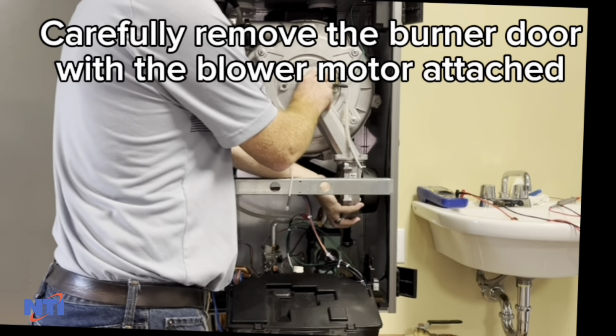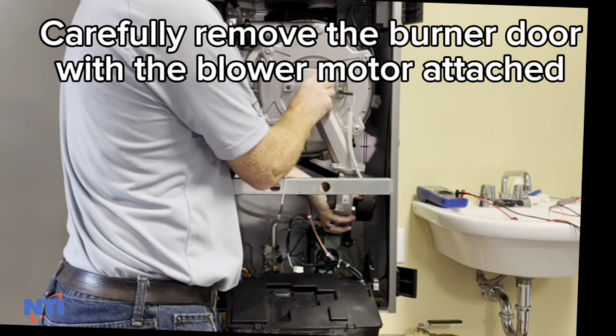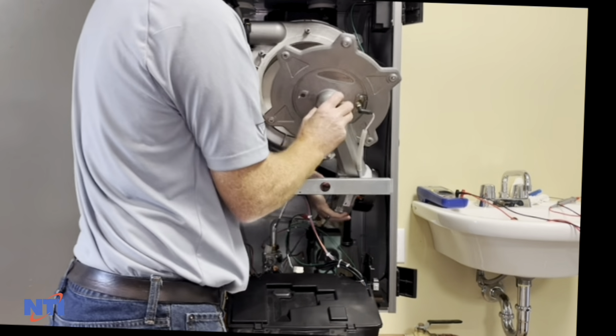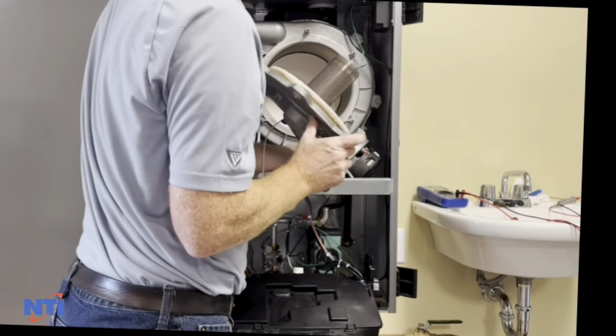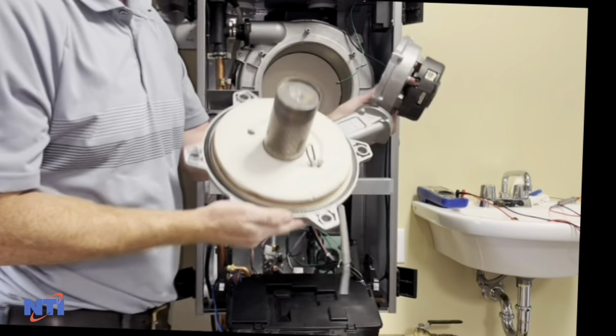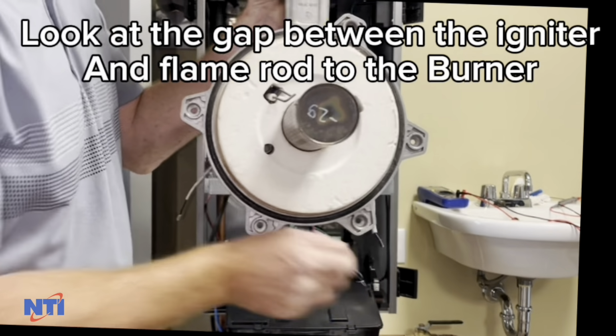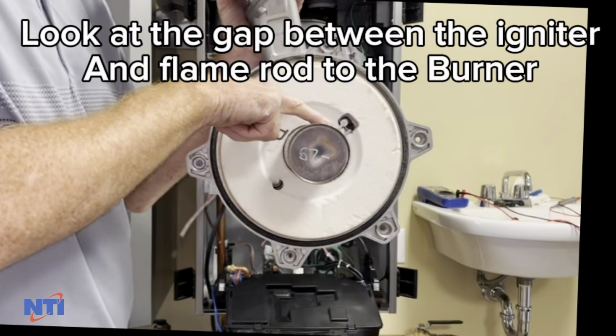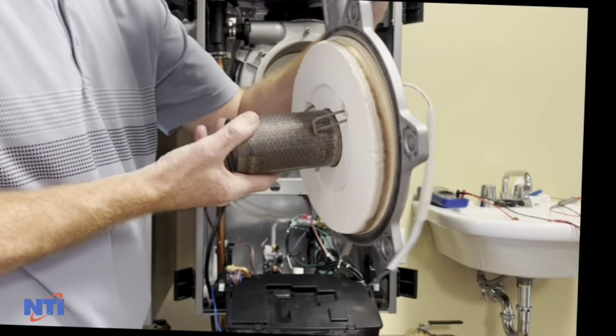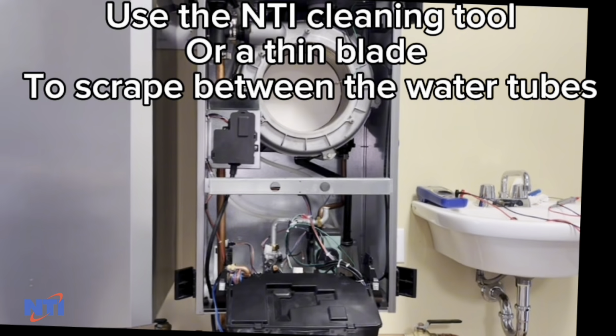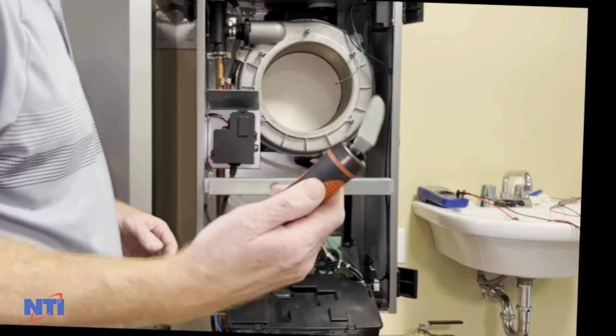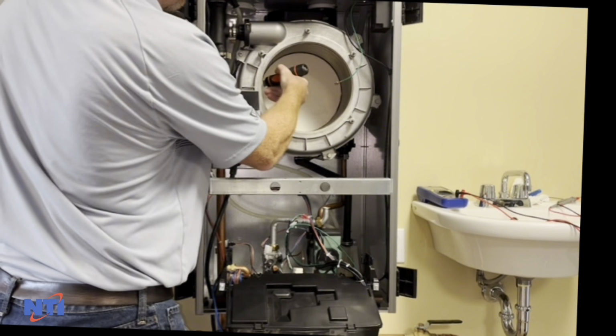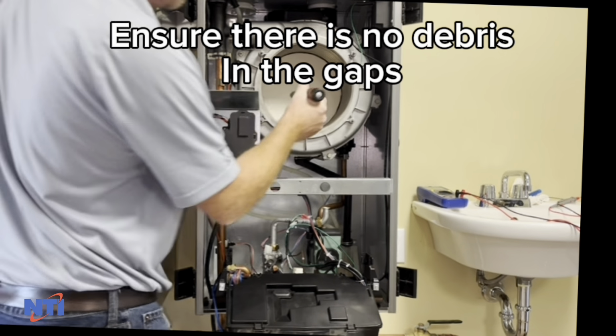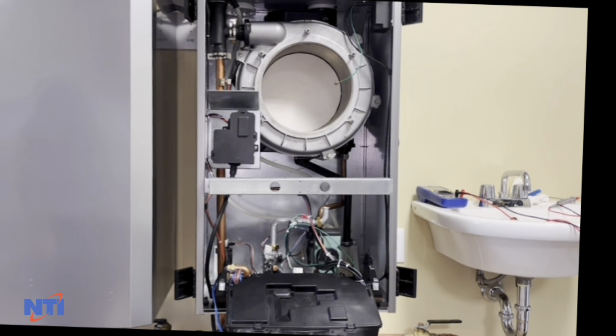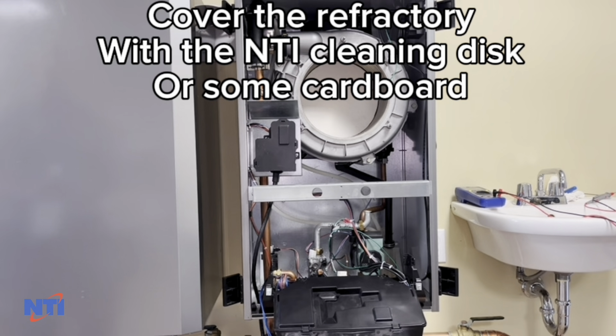Burner door is off. Inspect the refractory for cracks, damage, or watermarks. Look at the gap between the igniter and flame rod and the burner itself. Also inspect the burner for signs of clogging or dirt or debris. Using a cleaning tool like the NTI Boiler cleaning tool or a thin metal or plastic card, scrape between the tubing to ensure that there is no debris.